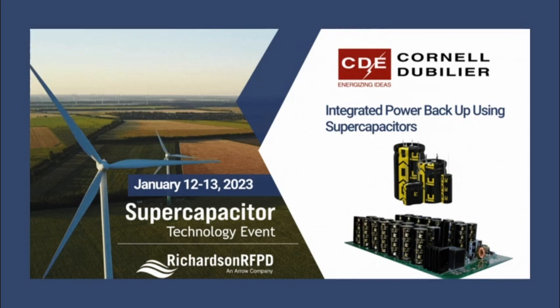Batteries have been used for backup devices for a long time. They can primarily be considered to be a voltage-based power solution — their voltage will remain stable during discharge over a fairly wide range of load currents and only begins to drop sharply at the end of the battery's charge life. Supercapacitors, on the other hand, store energy in an electrostatic form. The voltage drops as the current flows and is essentially linear, so they can really be classified as a current-based power source.